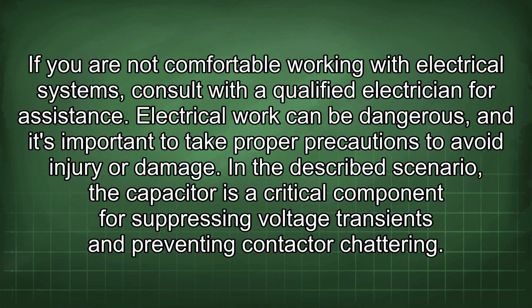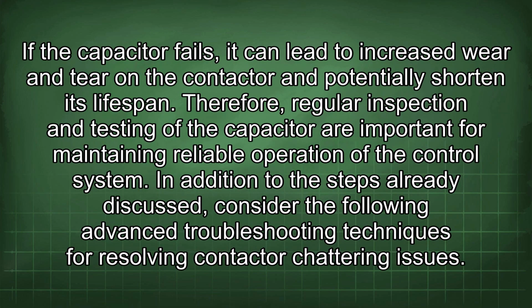In the described scenario, the capacitor is a critical component for suppressing voltage transients and preventing contactor chattering. If the capacitor fails, it can lead to increased wear and tear on the contactor and potentially shorten its lifespan. Therefore, regular inspection and testing of the capacitor are important for maintaining reliable operation of the control system. In addition to the steps already discussed, consider the following advanced troubleshooting techniques for resolving contactor chattering issues.